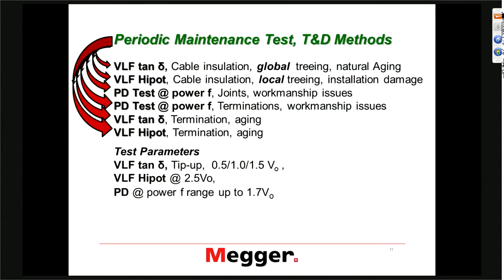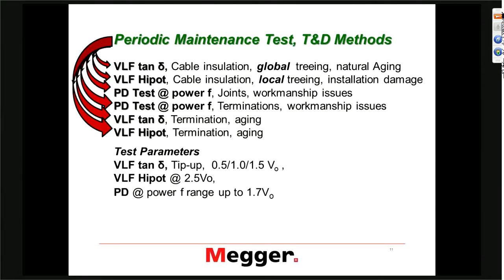For periodic maintenance tests, we can use VLF Tan Delta, typically perceived as the method of choice today to detect treeing in cable insulation, especially in XLPE cables. We can do a VLF hipot test to see cable treeing, but then it has to be at the point that it will fail — so it's not really a diagnostic test, it's more a go/no-go test. We can do a partial discharge test at power frequency to analyze joints and terminations.